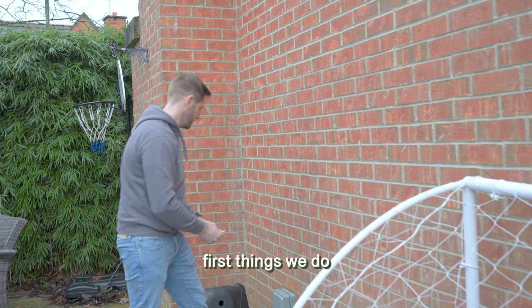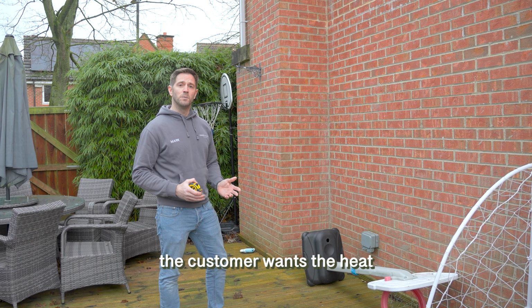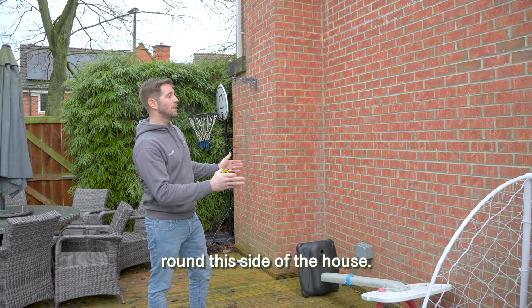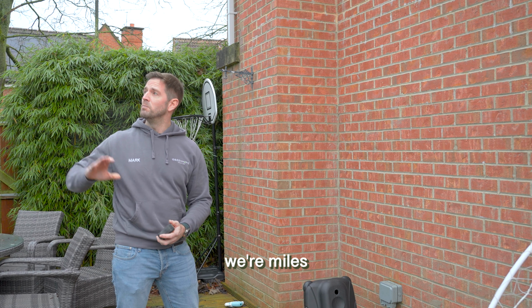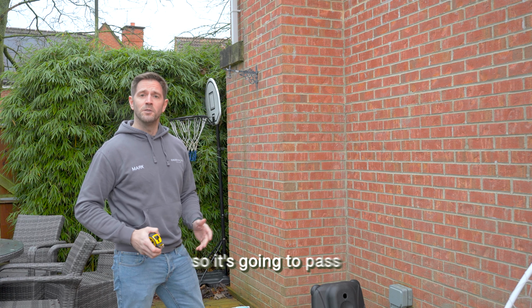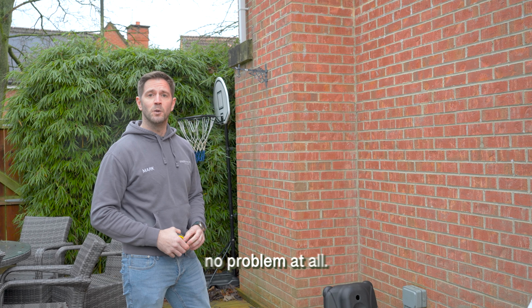So one of the first things we do when we get to the property is have a look at where the customer wants the heat pump to be located. So this customer wanted it around this side of the house. There's plenty of space here. We're miles away from next door properties, so it's going to pass the sound assessment no problem at all.